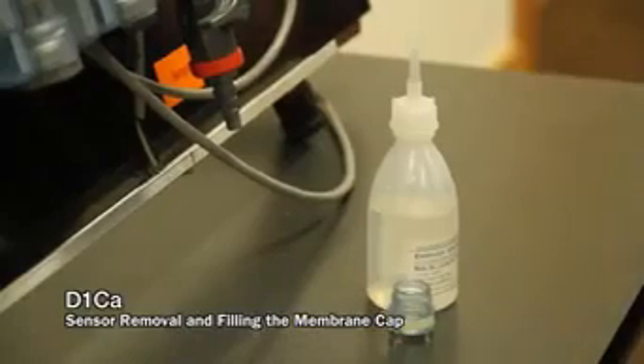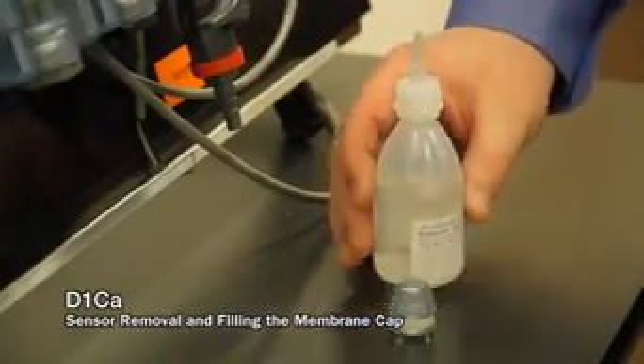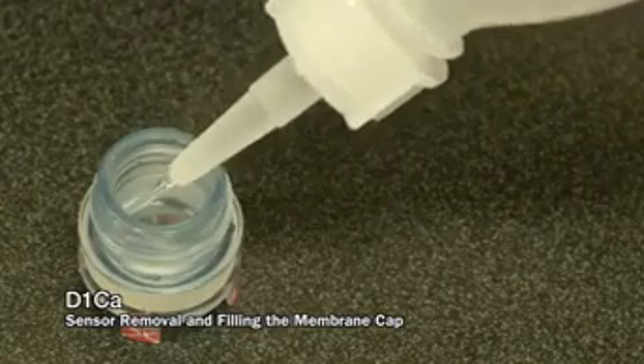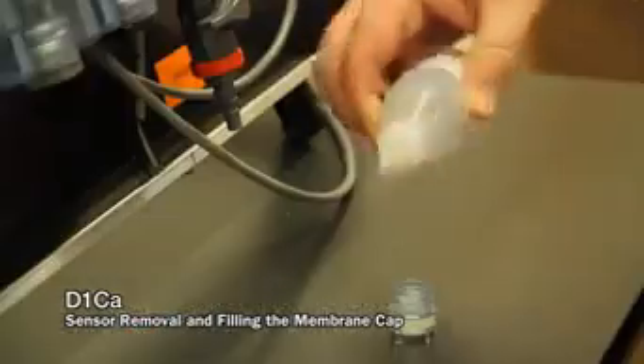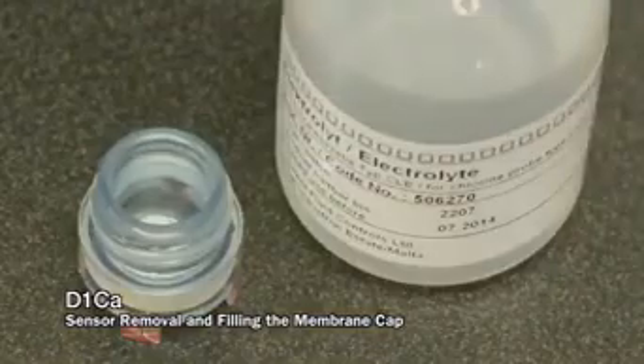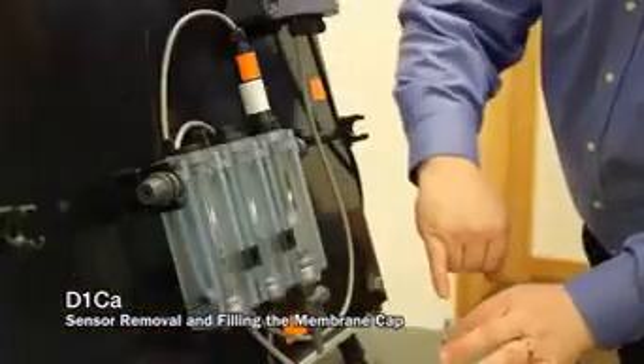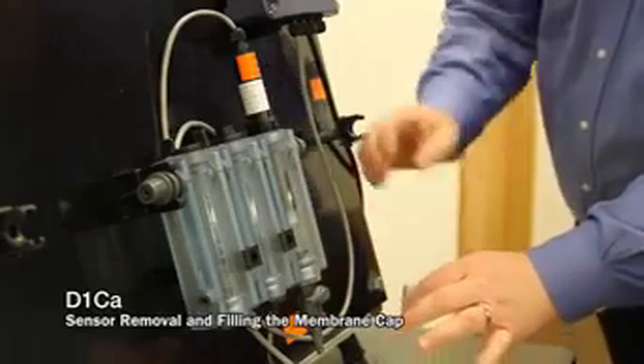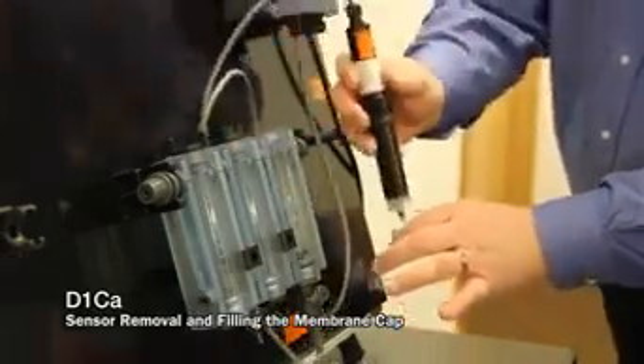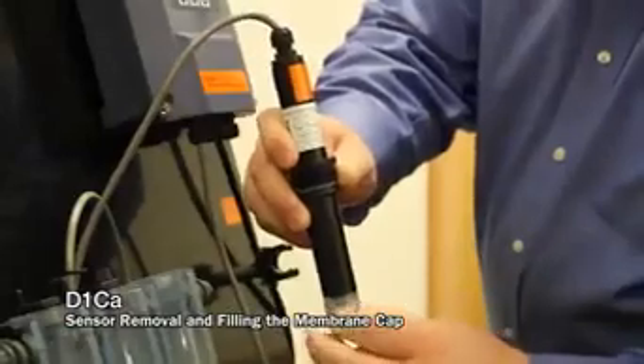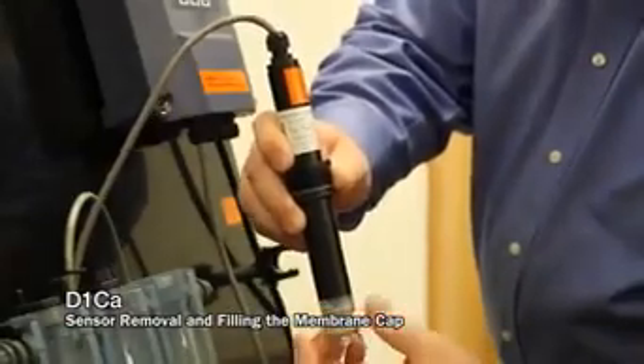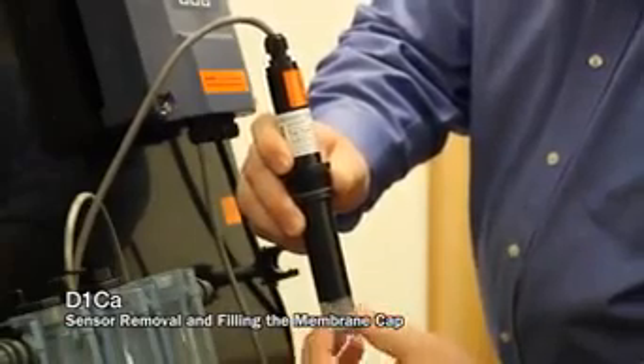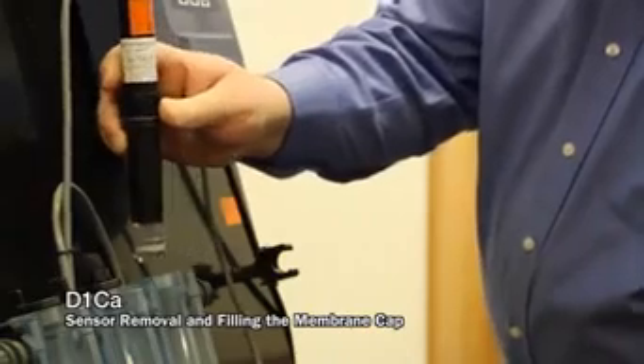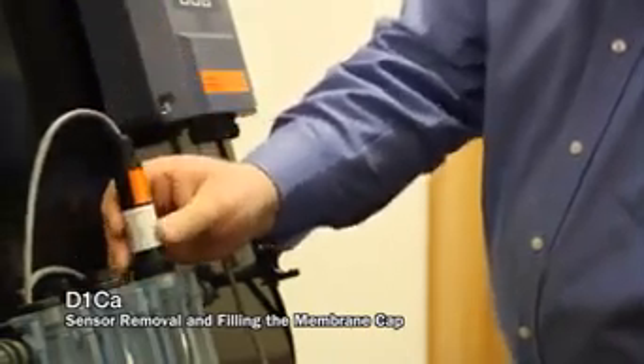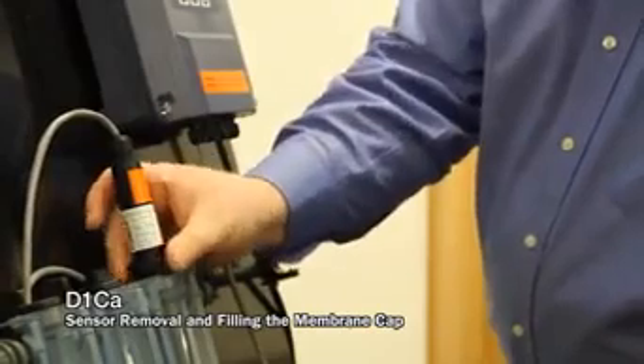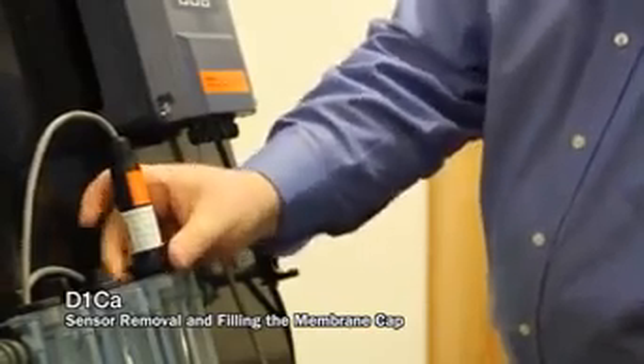Now this particular sensor has a very water-like electrolyte. We're going to fill that cap full. Be sure that there are no air bubbles down where the membrane is inside of the cap. Thread that cap back onto the sensor. Place the sensor back into its sample cell and tighten our compression fitting back in place.